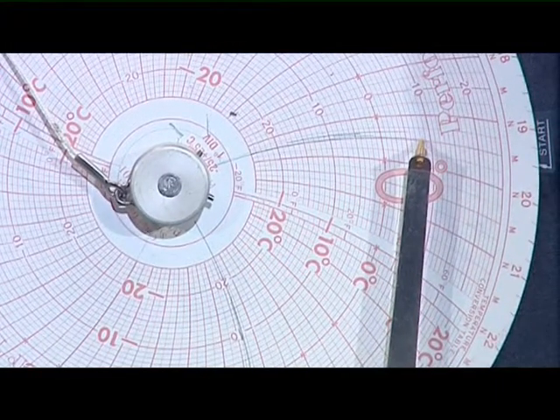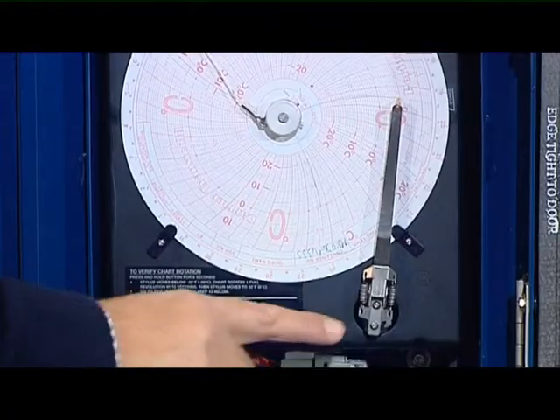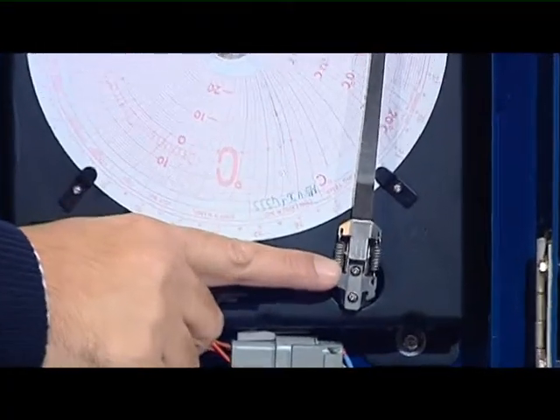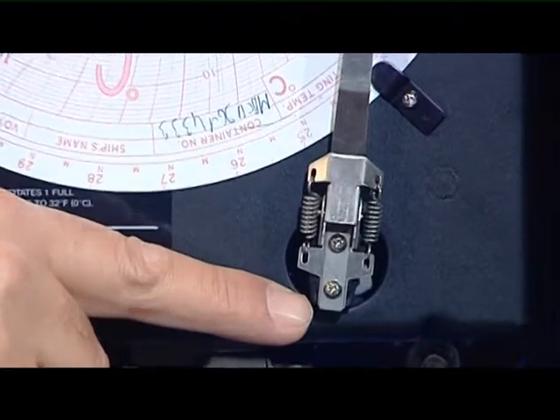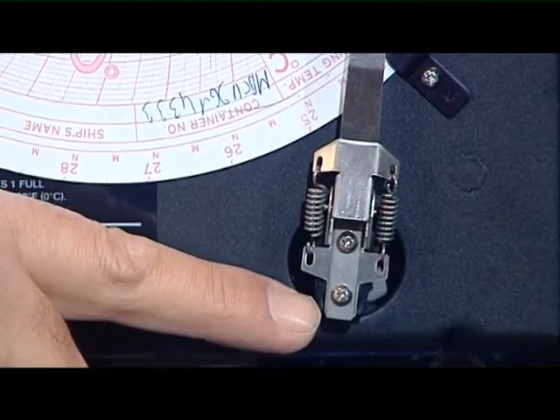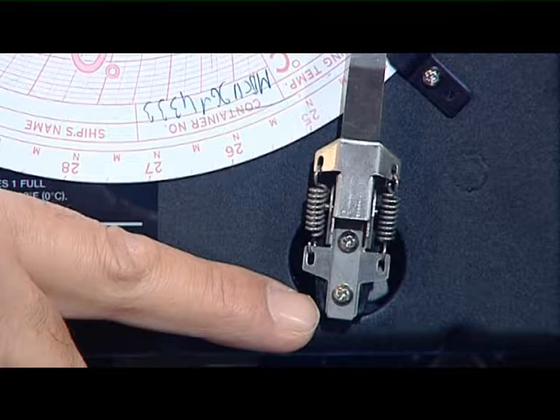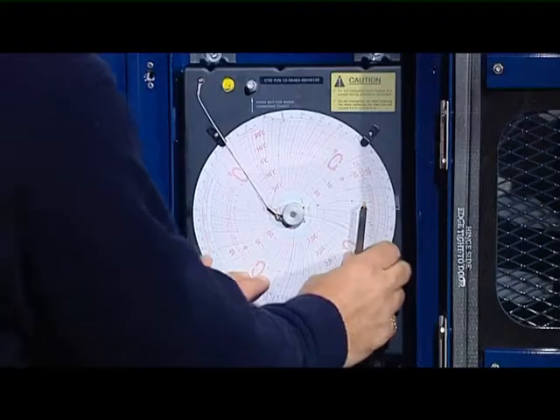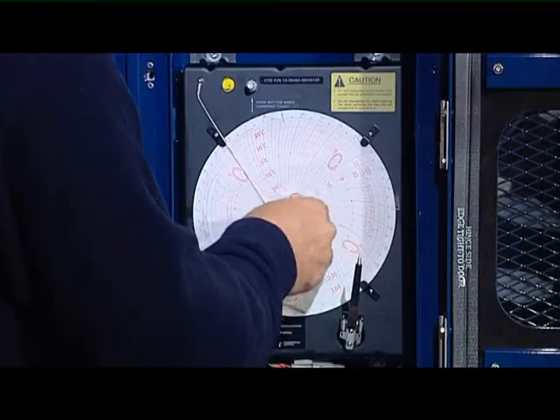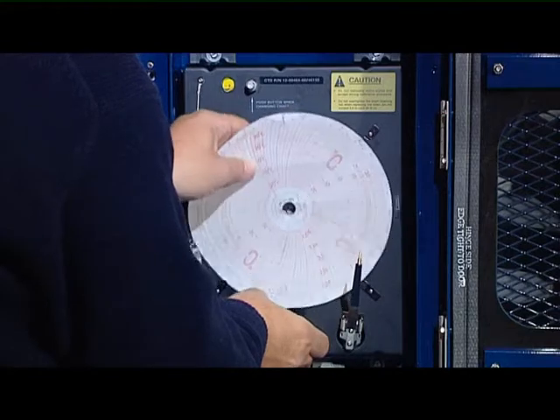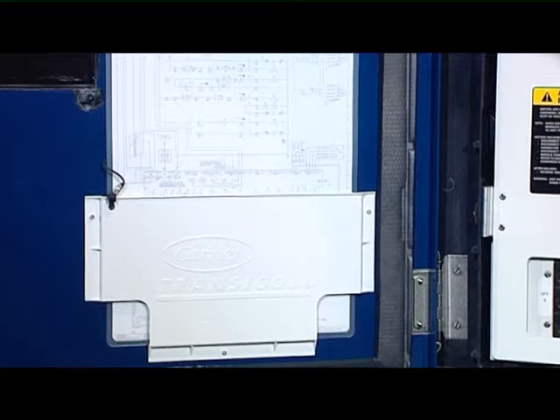If during calibration the pen is not marking 0, you'll have to adjust it manually by loosening both screws of the pen and placing it on the 0. Refasten screws and the adjustment is complete. When replacing the chart with a new one, always keep the original inside the electrical box, as it's often required at the discharge port.